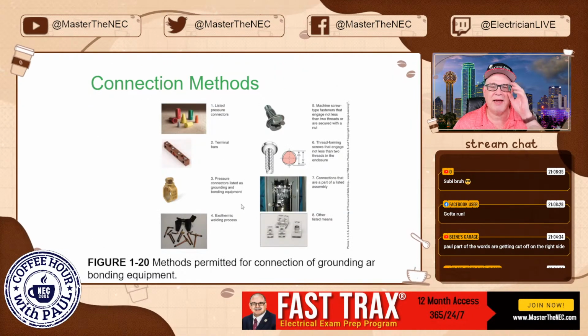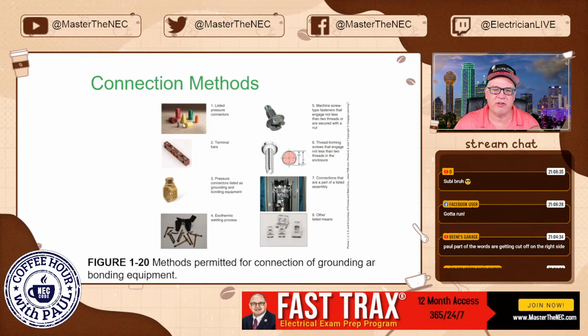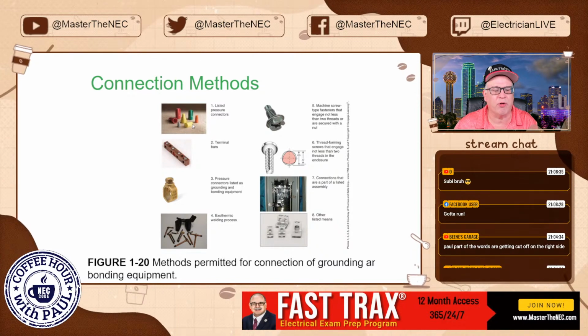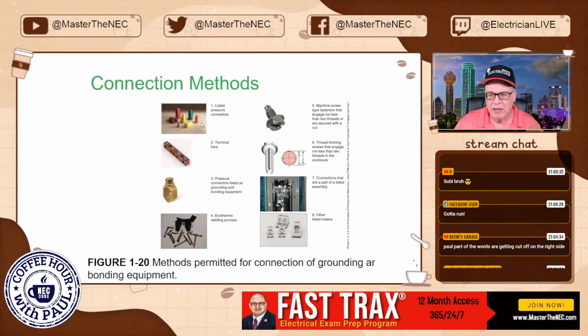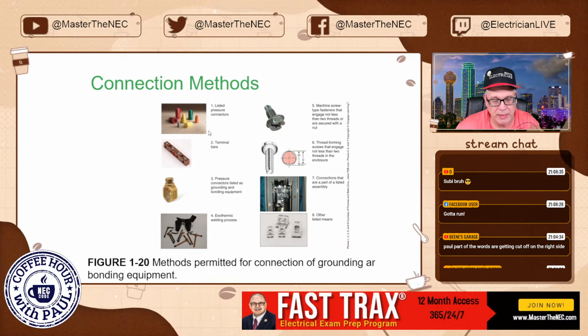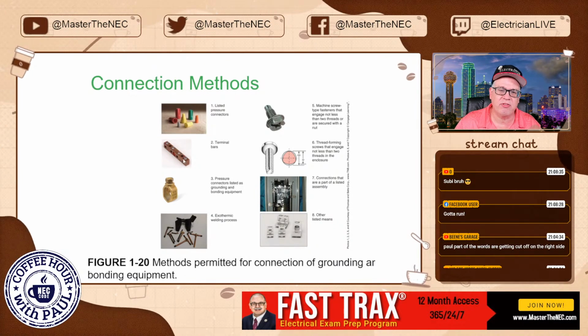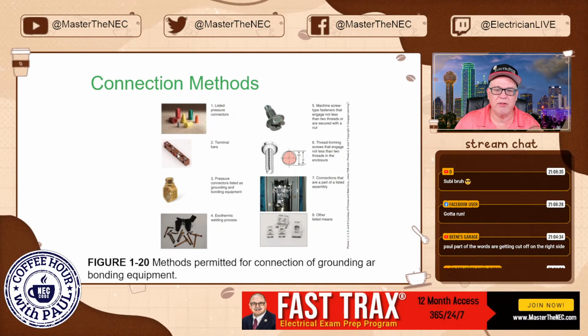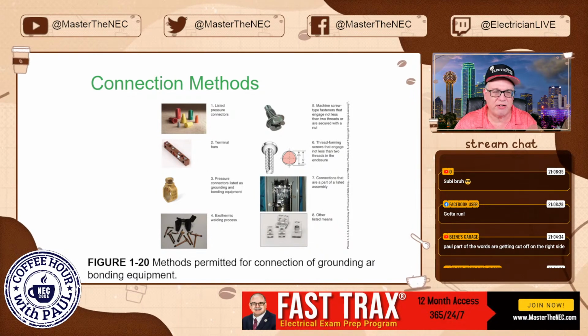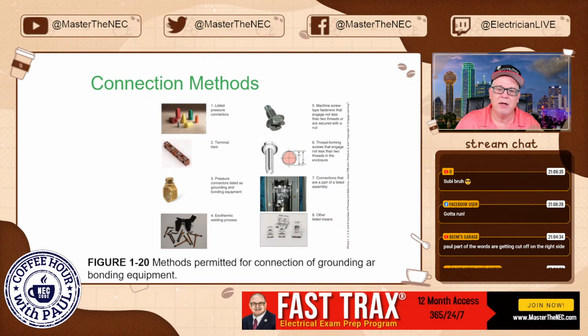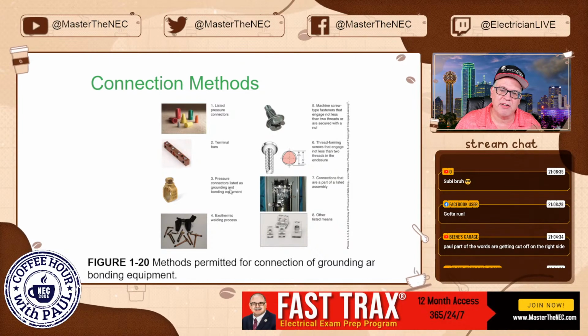All right, so here's your example. So here are your listed pressure connectors, wire bonding devices. People refer to these as wire nuts. It's a trademark by Ideal, by the way. Here's your terminal bar, okay? And this is what you see in the panels that you're going to make your connections, your equipment grounds to, and things like that. A pressure connector listed for grounding and bonding.